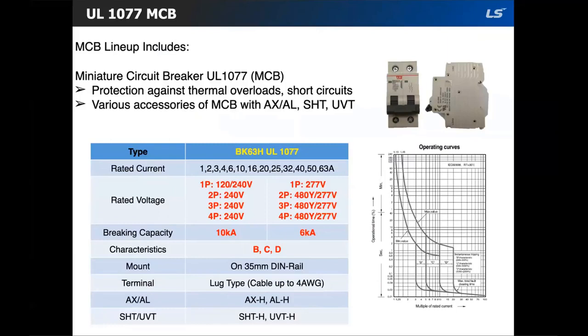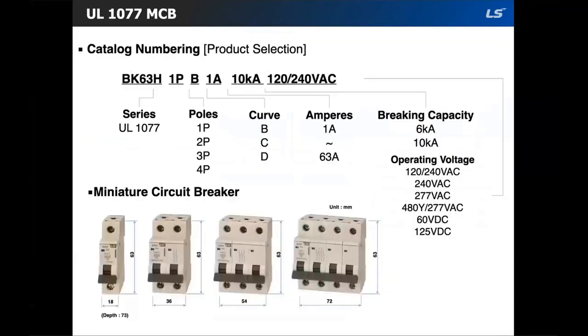So AX would be your aux contact, AL would be your alarm contact, SHT would be your shunt, UVT would be your under voltage. And here is the catalog numbering system. So the system shows the product code name, number of poles, your trip curve, your current, your breaking capacity, and then the voltage class. So these are dual rated voltage wise, so AC and DC.